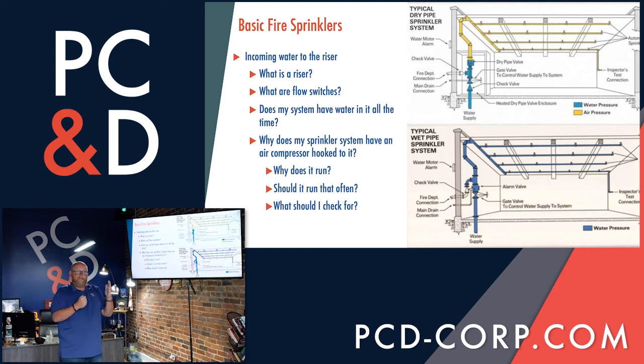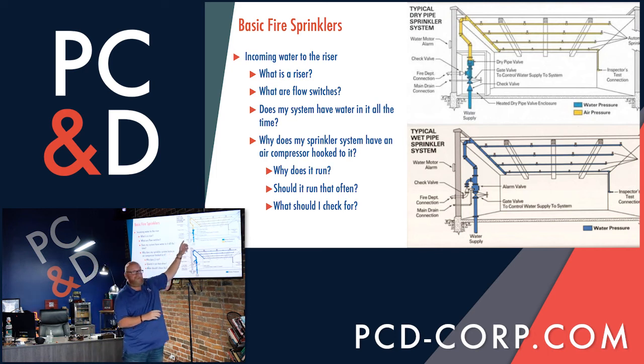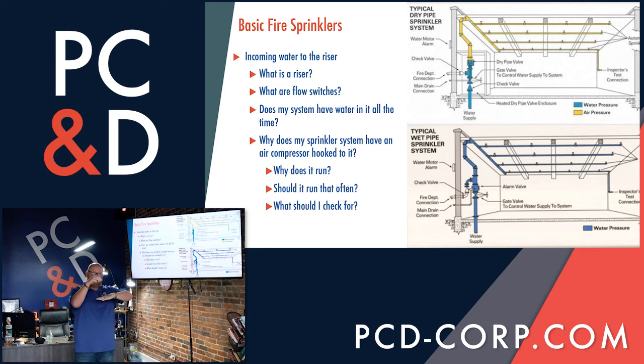So it's not like if it was to ever trip, you can just go, oh, I need to go fix that head. It'll all reset itself and the valve will come back down. That's not how it works. You have to have your fire sprinkler company come out, take the face off of this flapper valve cover, release the latch, close the valve, put everything back on, seal the gasket, bring the air back up, and then turn the water back on. So that's kind of a very basic understanding of how wet systems and dry systems work.